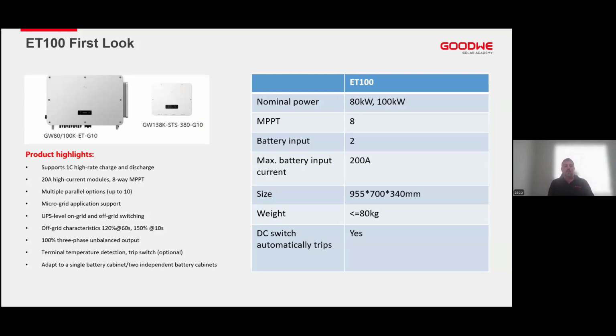This will be an extension to the ET series, with the target market segment being from 100 kilowatt up to 1 megawatt. So following the trend of the ET50, there's 2 nominal power ranges. So it's either 80 kilowatt or 100 kilowatt unit. Again, in South Africa, we will predominantly focus on the 100 kilowatt unit. In comparison with the ET50, which has 4 MPPTs with 2 strings each, the ET100 will have 8 MPPTs with 2 strings each, and also 2 battery inputs with a battery input current of 200 amp.